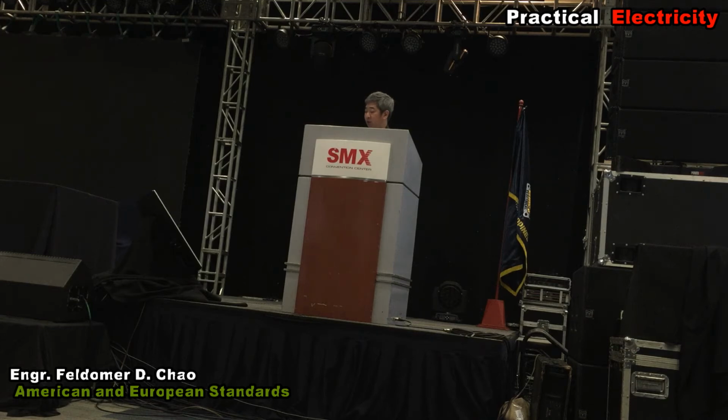EPR they have both, but the Americans don't have an HP EPR. For the BIL at 35 kV, the Americans have a 200 kV BIL requirement, and for IEC it is just 170 kV.